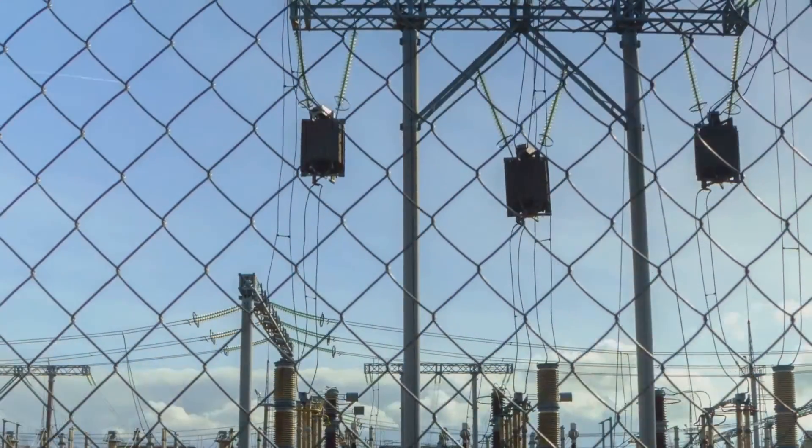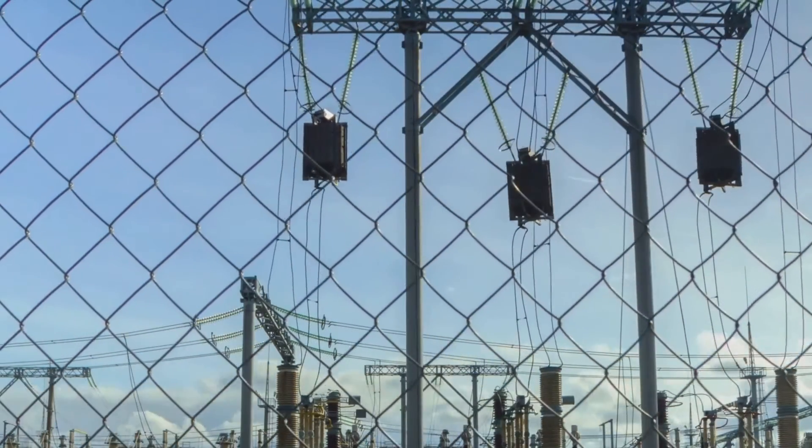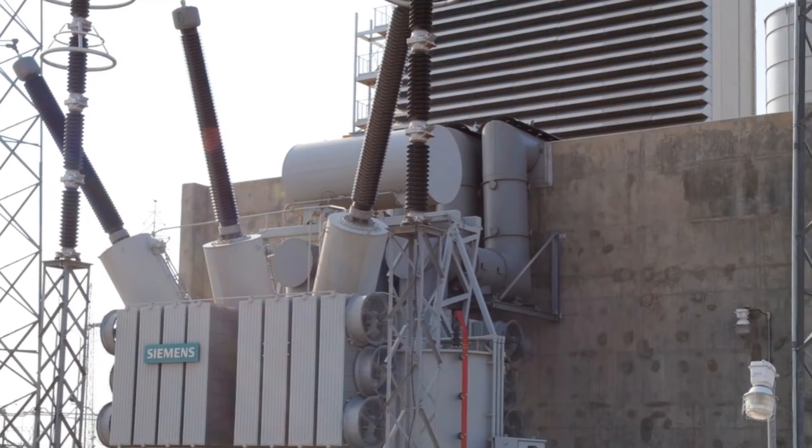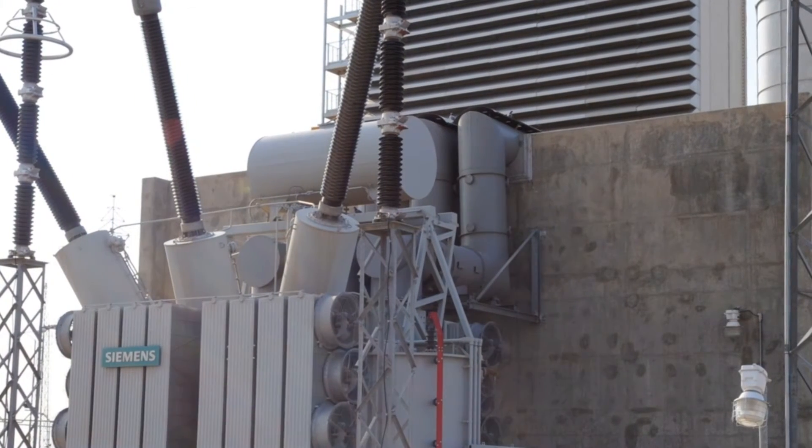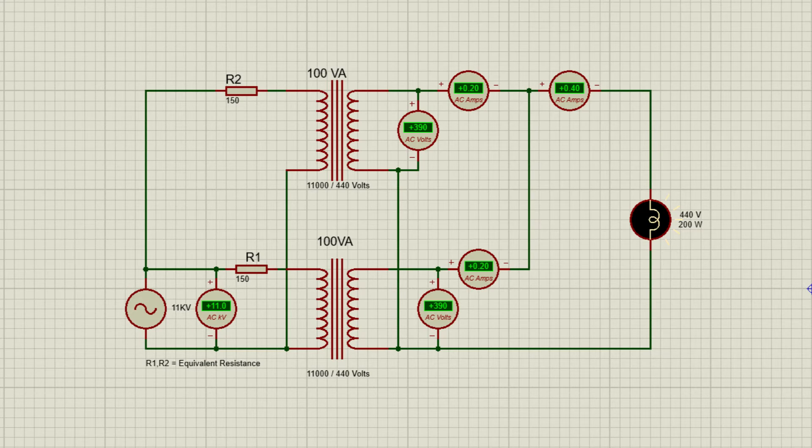And what about the role of percentage impedance in the parallel operation of transformers? Well, transformers often operate in parallel to maximize their utility. In an ideal world, when transformers run side by side, they should share the load equally to prevent any unnecessary circulation of current from one transformer to another.